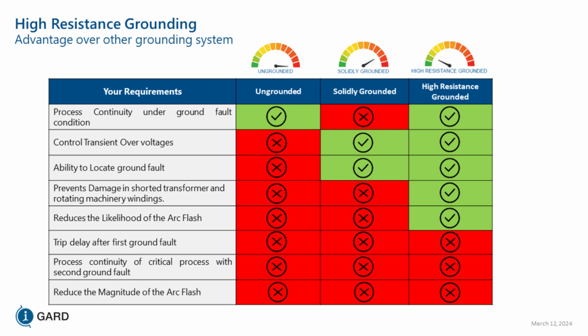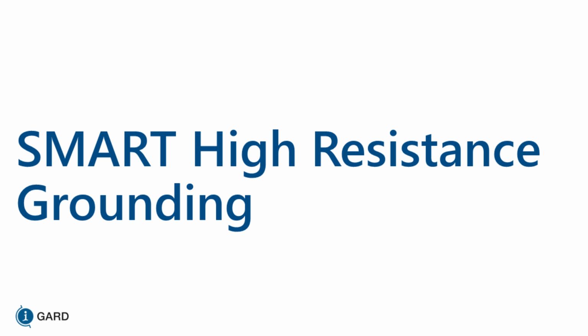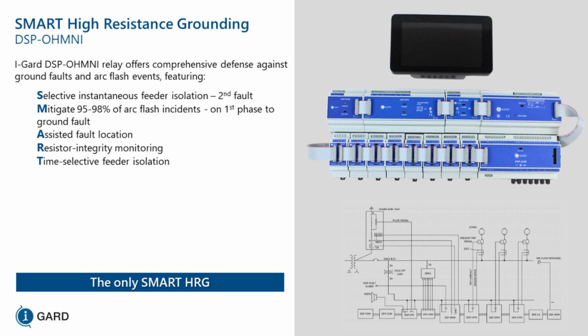We've actually put CTs around conduit, and we can actually locate the pulsing in the ground fault circuit. It prevents damage to transformers or rotating machinery, and reduces the likelihood of having an arc flash. So these are the advantages you get with a high resistance system. But that was just a regular high resistance grounded system. We've also developed a smart high resistance grounded system where you have selective instantaneous feeder trip.